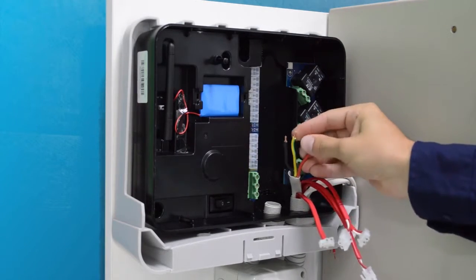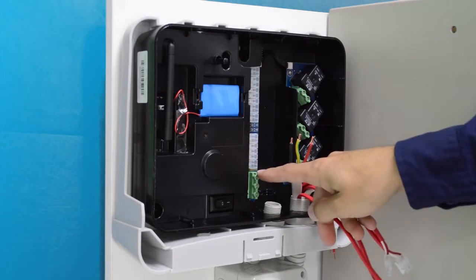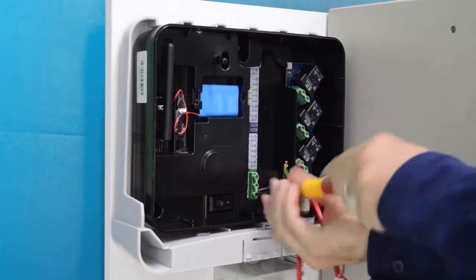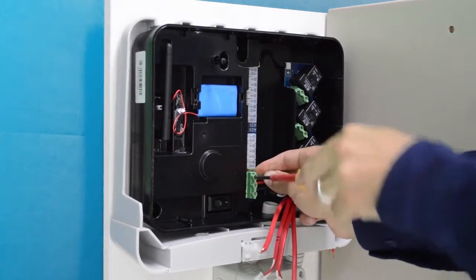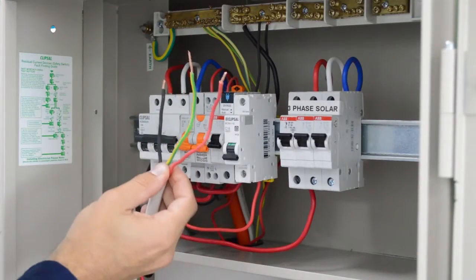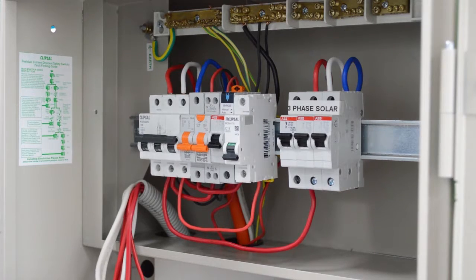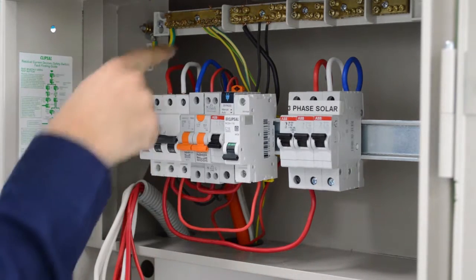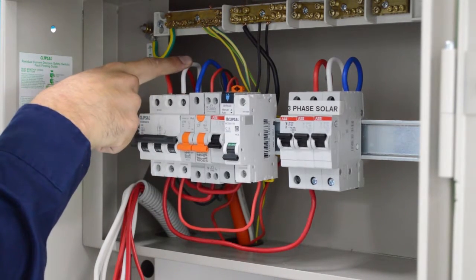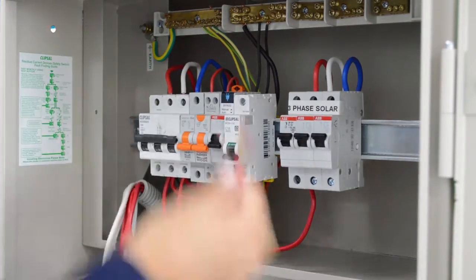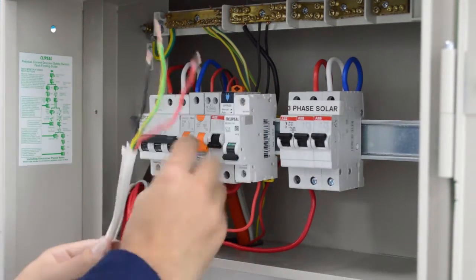Terminate the twin and earth at the unit into the main terminal provided. Terminate the twin and earth at the switchboard into a suitably rated breaker. I'd like to point out that with the suitably rated breaker, you must take note of which phase that breaker is connected to.